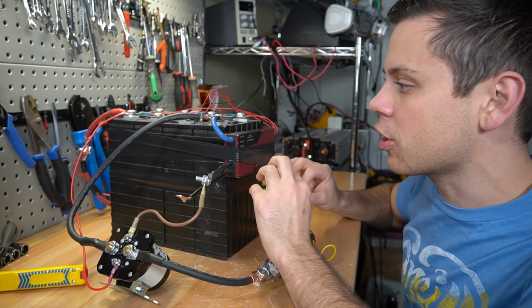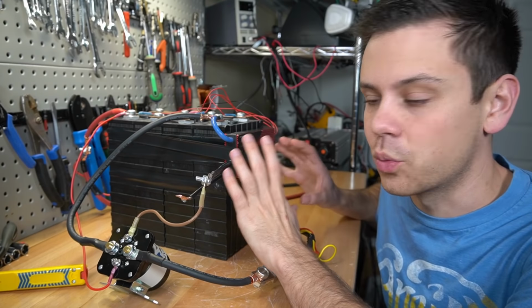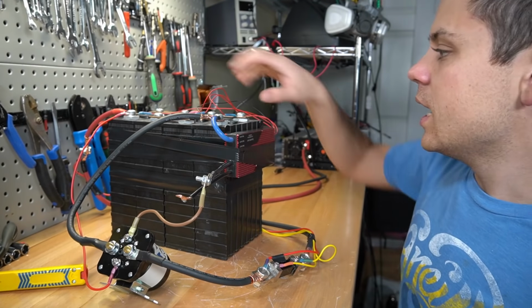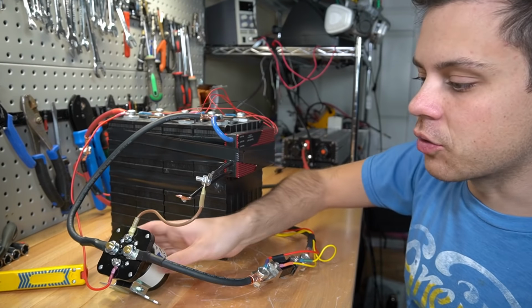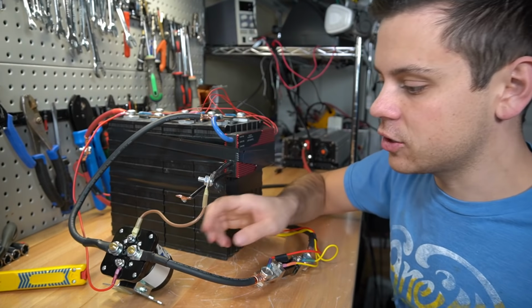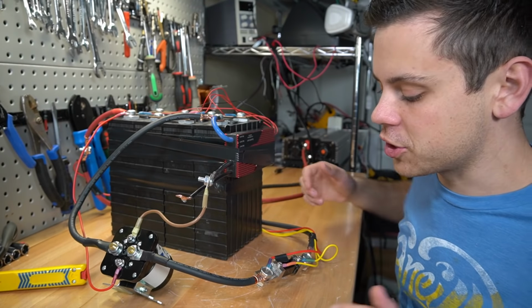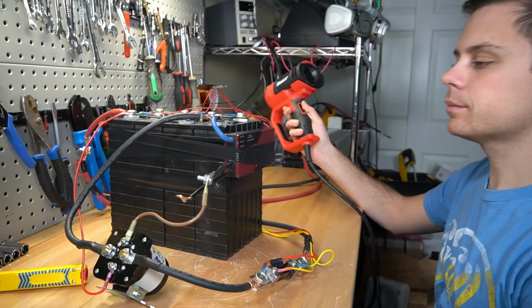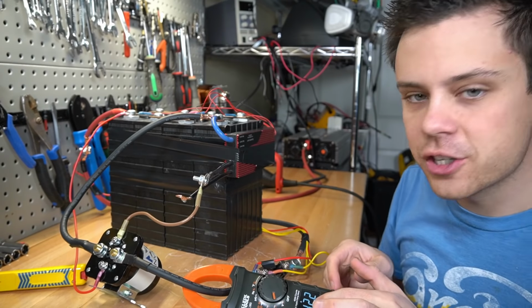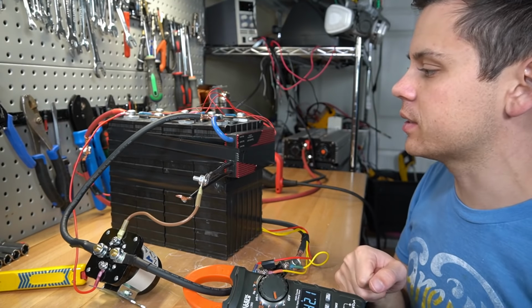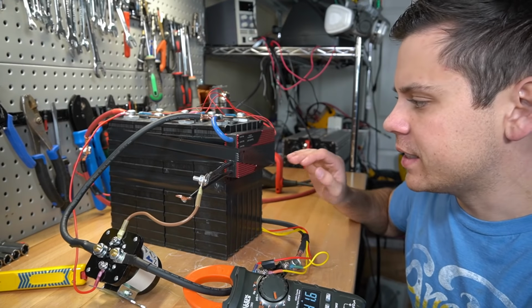So we need to ensure that our low voltage disconnect system works, so we're going to test it out. Right now the BMS is connected and the relay is in an on state, meaning the inverter can be switched on, so let's do that. We're pulling 142 amps continuously, so we're going to run this battery until it dies.